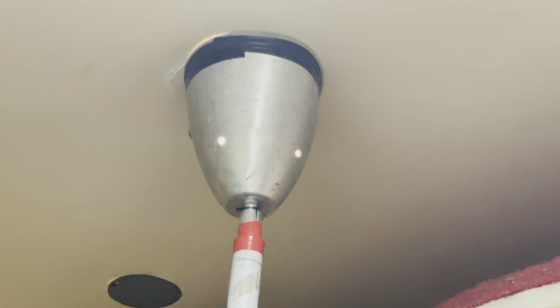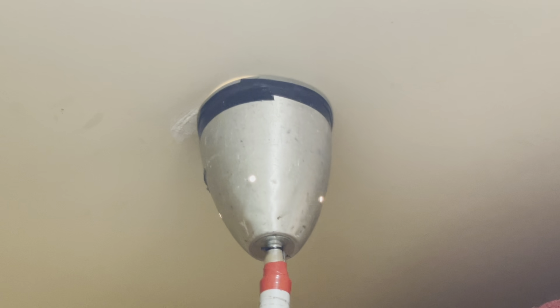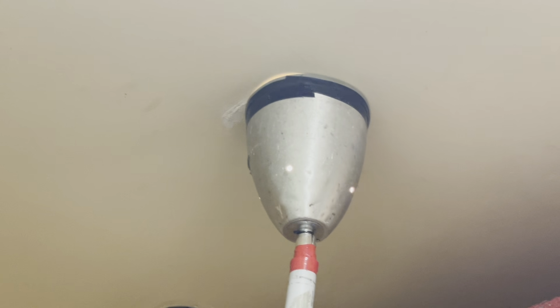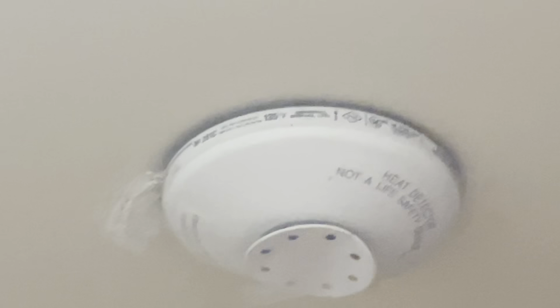But we've done the front one twice now and it doesn't seem to set off, but we hear the click from the relay. So I'm on there again. Reset here. The one actually in 1019 doesn't want to go off. Edwards 281 series, eh? I guess that's why they're recalled. You know, the majority of them... What kind is it? It's the old Edwards, but it's not going off, and I've had it on there now for two minutes. It's not going. Edwards 281C.